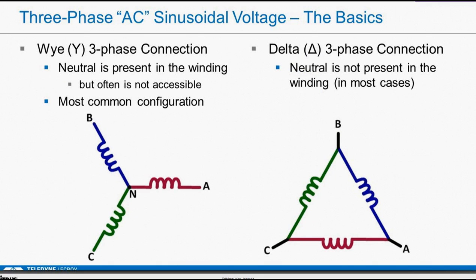Okay, so it's also good to know that to achieve this three-phase, there could be a variety of different connections. I've shown this here as a coil, like you'd have in a motor or a transformer. This is what's called a Y, because it resembles the letter Y. The neutral point is in the middle here, and the line side is on the outer end of the winding. This is most common, I think, overall, especially in motors, but quite often the neutral is not accessible. It might be buried. So it's connected, but you can't get to it for measurement purposes. That's why a lot of people just measure line-to-line voltage.